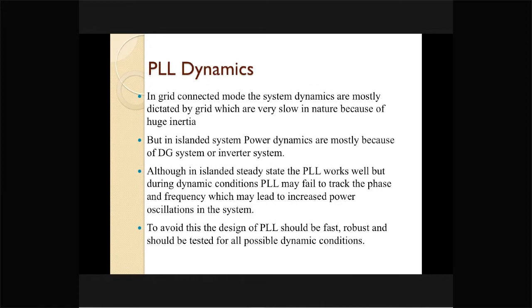system. And that inverter, which is now getting its reference signal from the PLL, will be in an unstable mode of operation when the grid voltage has a power quality issue. That means the voltage of the grid is not absolutely sinusoidal, but has distortion imbibed into it. Therefore, the PLL dynamics in a grid-connected photovoltaic system need to be properly looked into, and the dynamics integrated with the grid behavior is a research topic that needs to be seen in depth.